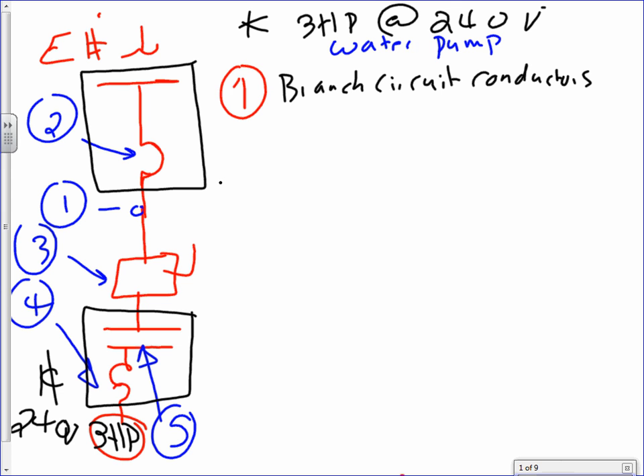Branch circuit conductors. I need to size the branch circuit conductors. That's number one, the branch circuit conductors. Before you size the branch circuit conductors, guys, you need to find the following. You need to take the 3 horsepower at 240 volt and find the full load current from table, and I'm going to write tables here, table 430, and I'm going to go directly to this 248.